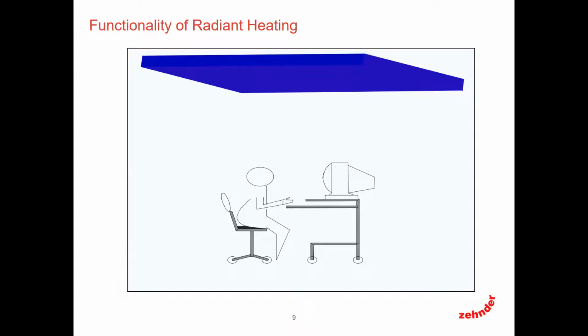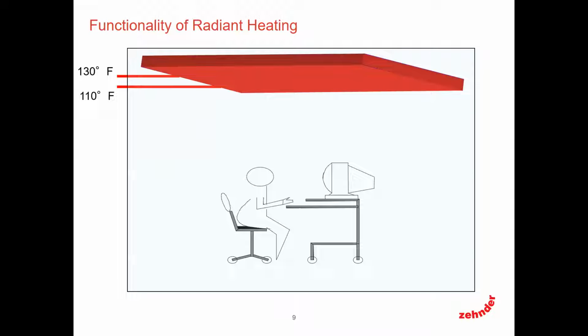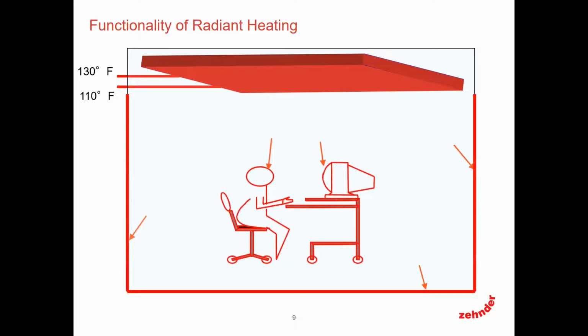And it's very, very important that we remember this as we move forward. All right, so radiant heating, and don't get hung up on the water temperature so much. I really want to just simplify this. So as your hot water comes into your conditioned surface, the surface itself becomes heated. It gives off electromagnetic waves. It then turns and hits the objects themselves. Those objects in turn then heat the air. What I didn't say, and I want to point this out, was the controlled surface heats the air and then heats the occupants. It's very, very important to remember this as we move forward, because I'm going to talk a little bit about ASHRAE 55 and thermal comfort and what that means.